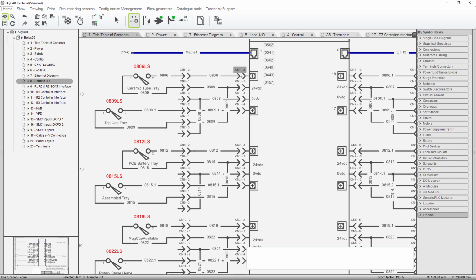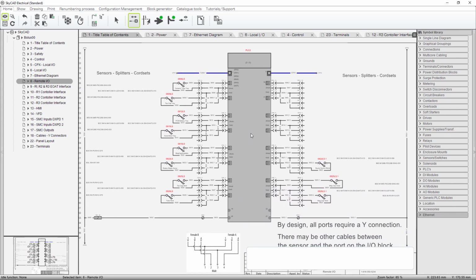And notice that the connectors, they are automated. In other words, see, this one says connector 1, connector 2, connector 3, connector 6, 7, 8, 9. So this automates that whole process. Now you do have to create a connector in the database, and then you click on this and say this belongs to connector 1. That's why you see the pin numbers. That's pin 1 and that's pin 2. Well, that's irrelevant because remember, this is one solid physical device that screws into this armor block, and then these are probably cables, 3-wire cables that plug into these 2 connectors. Okay, so that's remote I/O.